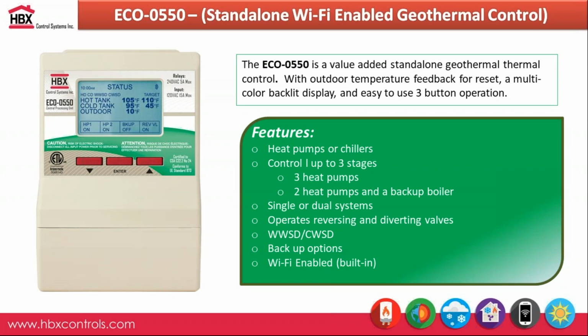So we can do 3 heat pump stages, or 2 heat pump stages and a backup boiler. Again, we can do single or dual tank systems, both with outdoor reset. That's a nice feature with the Eco 550, that we also have outdoor reset for cooling as well. Again, warm weather and cold weather shutdown options, and a couple of different options for how you want that backup boiler to come on.